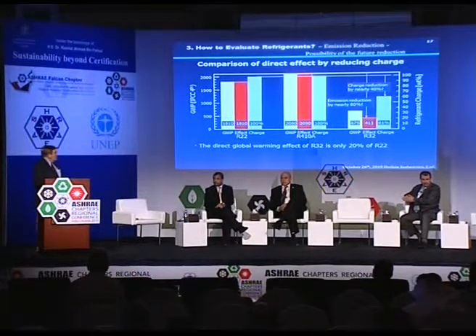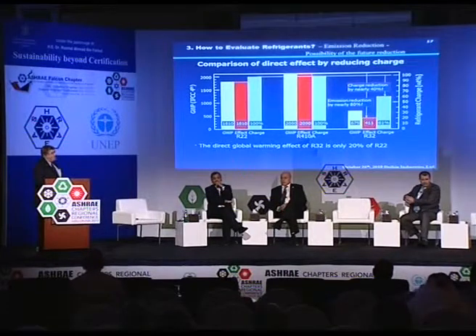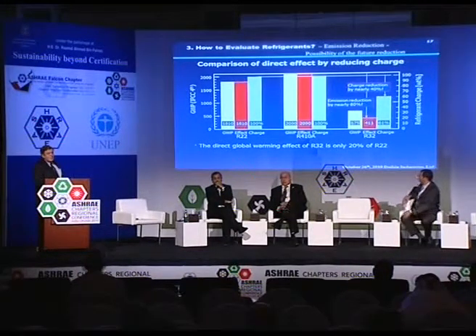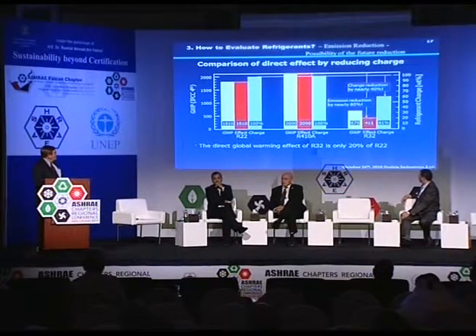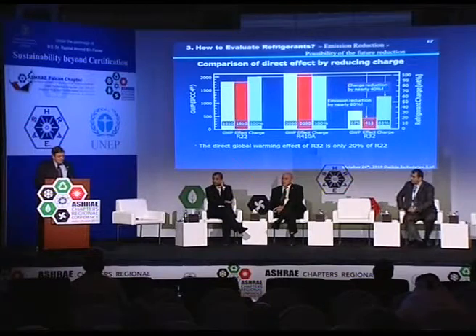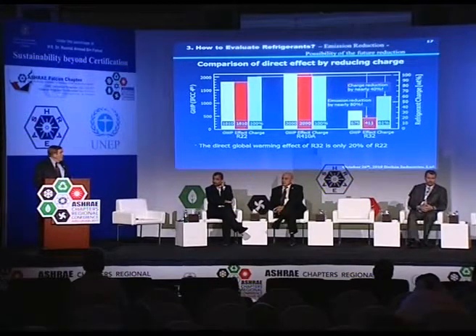If we take a typical system of R22 or R410A, with global warming potentials of 1800 and 2090, and instead use an R32 system, which starts with a much lower global warming potential, and then reduce the charge by 40%, we could reduce the global emission rate by 80%. So we not only have to pick the right refrigerant, but also design the equipment to minimize the charge.